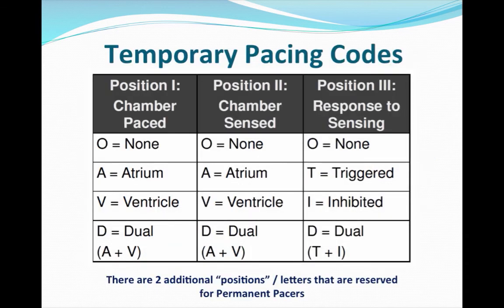There are different modes for pacing using a three-letter code. The first letter is the chamber being paced: O for none, A for atrium, V for ventricle, D for dual. The second letter is the chamber sensed: atria, ventricle, both, or none. The third letter is the response: O for none, I for inhibit, T for triggered, or D for dual (both triggering and inhibiting). Two additional letters exist but are dedicated to permanent pacemakers only.